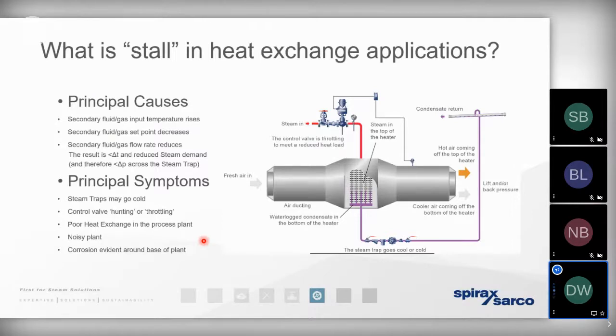If it was a very warm day outside, let's say 20 degrees outside, but let's say we just needed to top the temperature of the air up to 25 degrees, we'd only need to add a very, very small amount of energy. That means that we only need the steam to exist at a low temperature. Because of that pressure temperature relationship, it means that that steam could exist in these coils at very, very close to atmospheric pressure. And if we've got a huge back pressure on the condensate infrastructure, that could mean that there is insufficient pressure in the steam to push the condensate out of the heating coils, across the steam trap, and energize it so it can travel back to the boiler house.